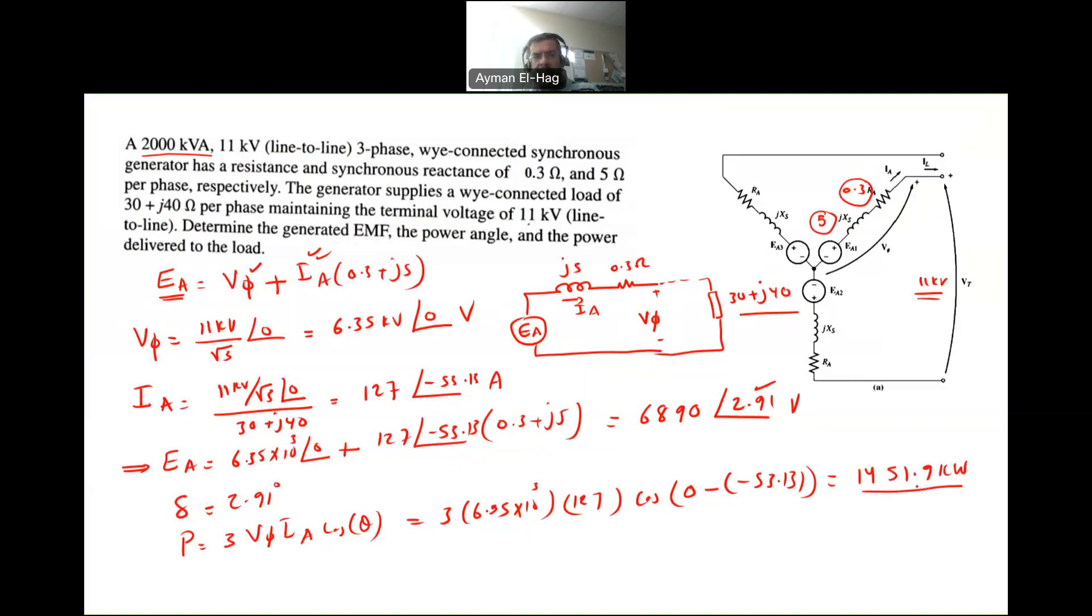So this is how much power I can get from my generator, 1451. Now, the power factor of this, that's not required in the question, is equal to cosine 0 minus minus 53.13, which is equal to 0.6. This is the power factor. So at this power factor, the P rated of the generator is equal to the 2,000 kVA times the 0.6, which is equal to 1,200 kilowatt.